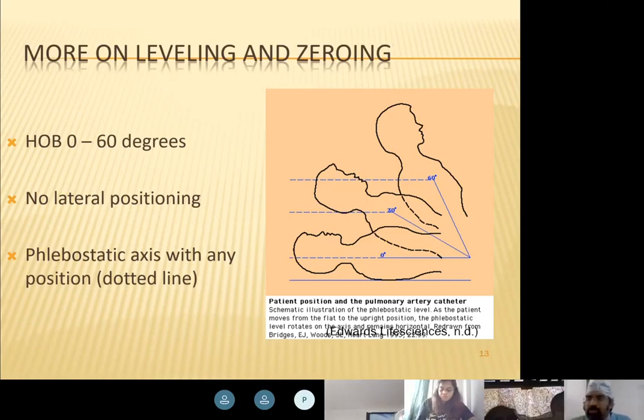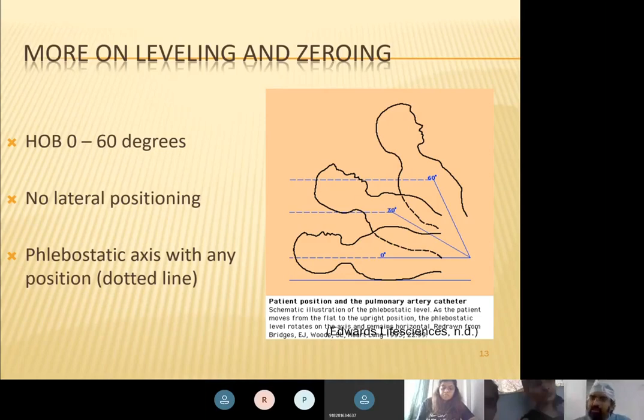So if the transducer goes down to the ground, your pressures will go very, very high. Your blood pressure will read very high. If the transducer goes higher, the pressure will read very, very low. It's as simple as that. That is why if you suddenly find the pressures to be very, very high, check where your transducer is. It might be lying on the floor. Clear on this? So when you do lateral positioning, again there will be a problem because the transducer will go down.